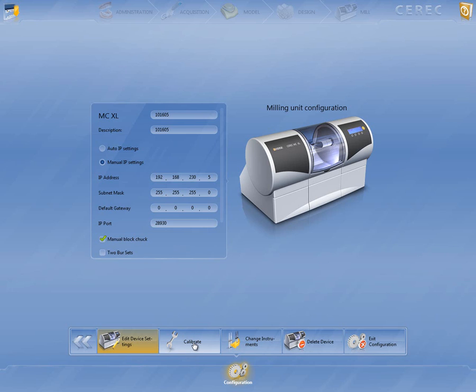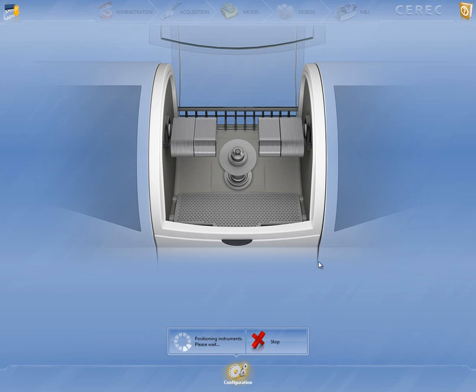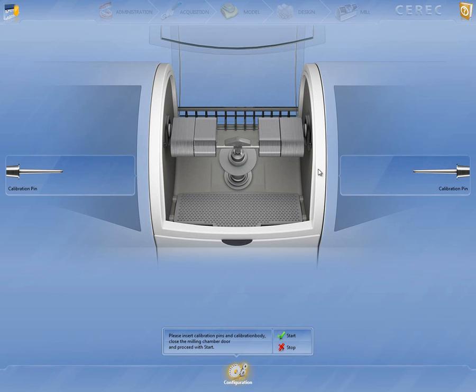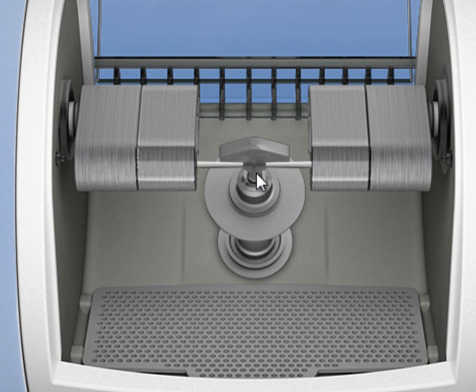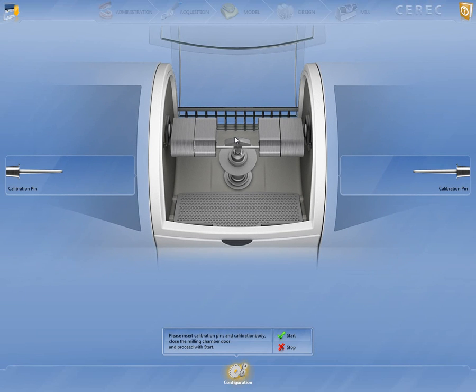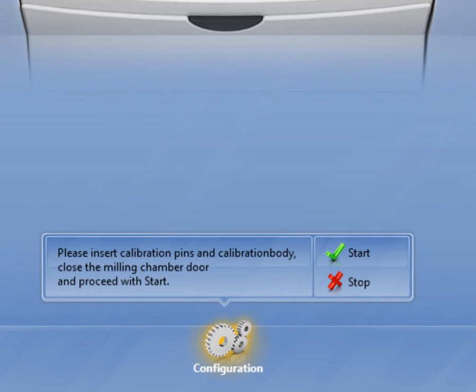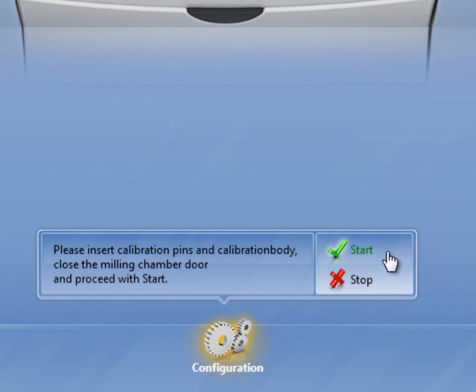So we're going to click in Calibrate. You hear the machine running in the background, and it's going to position the instruments. And if you notice, we have a calibration pin on both the right and the left. Then we also have the calibration specimen in the middle. You're going to go to the chamber, remove the burrs or the blocks, and put in the calibration pins. We'll show you a little bit of a movie on that. And then once you've got the calibration pins installed and the calibration set in the middle, you're going to hit Start. It's going to take about 3 to 4 minutes for this to go through its process.